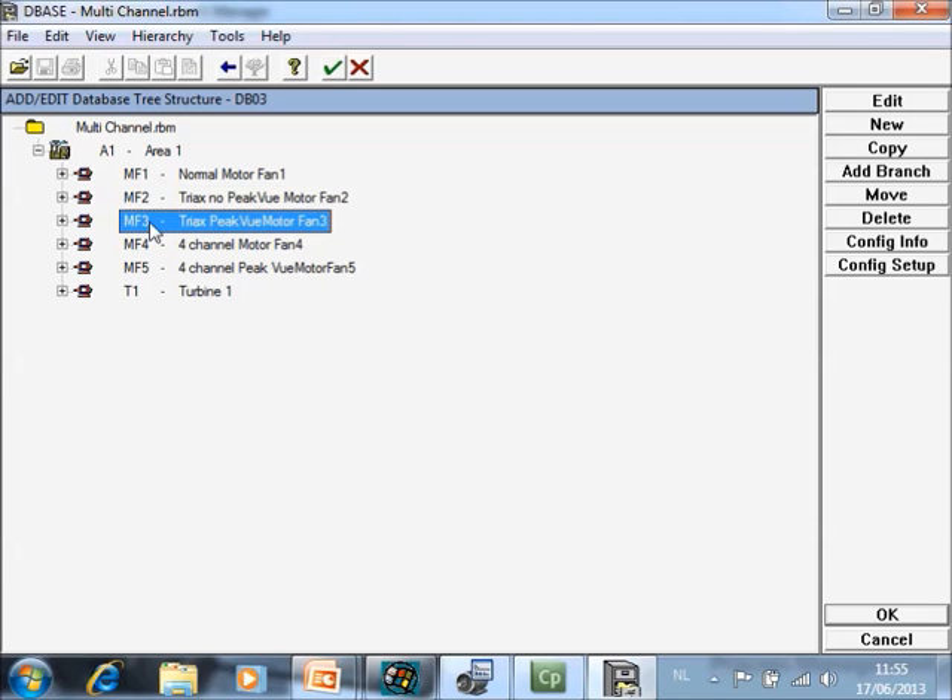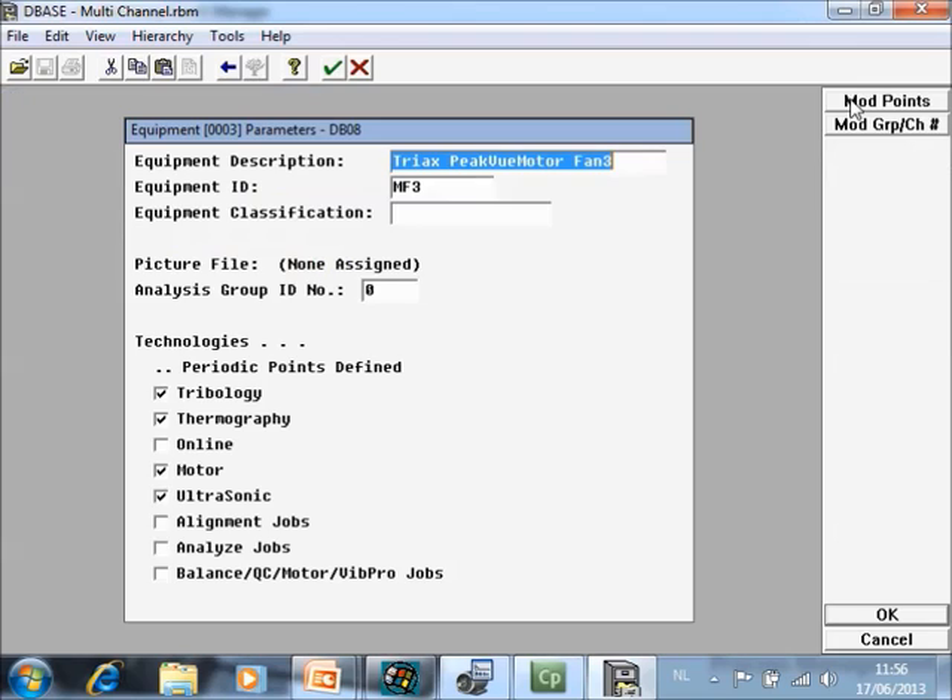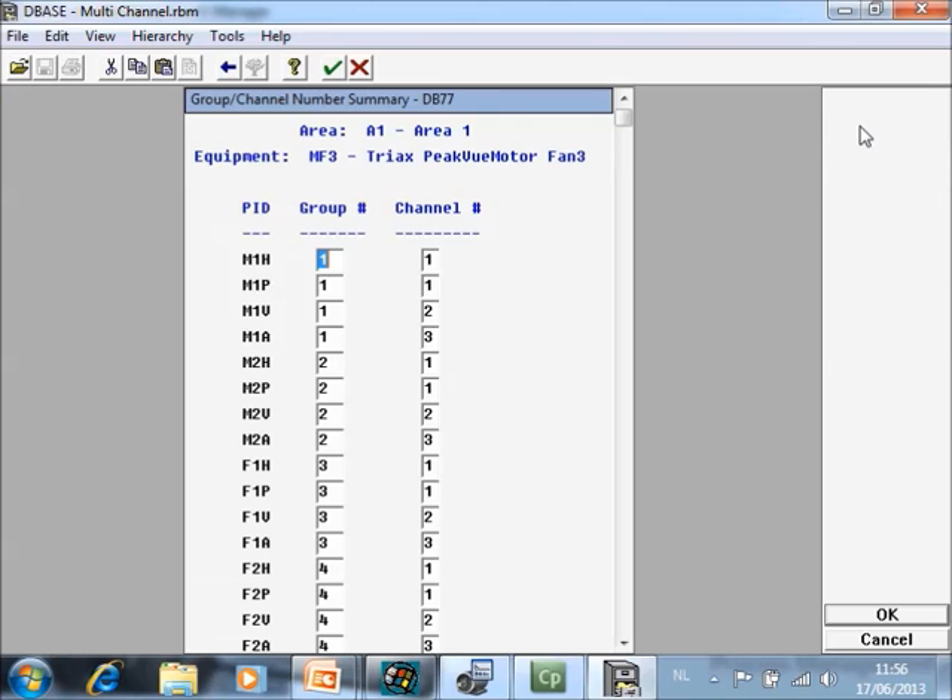If you also want to use PeakVue, here is an example of the same configuration but now with PeakVue. Go to edit, modify group channels, and the structure is the same except that everywhere motor PeakVue has the same group info and the same channel info as your horizontal point. That means the PeakVue measurement will be collected from your horizontal mounting direction.